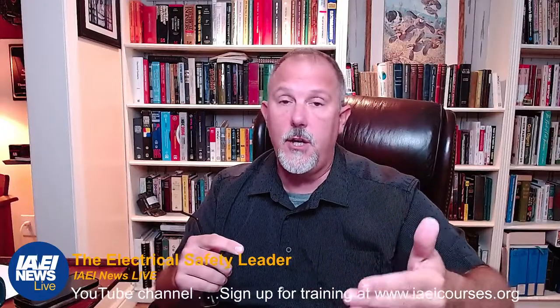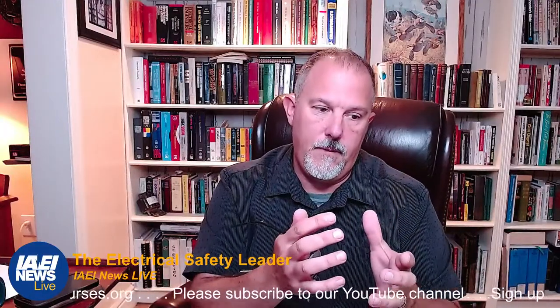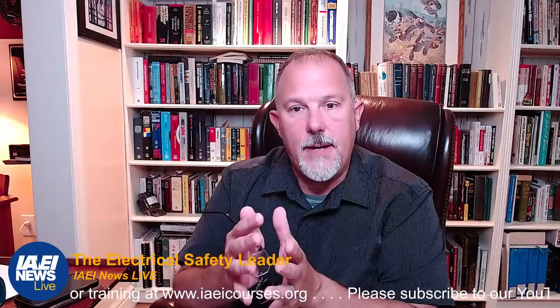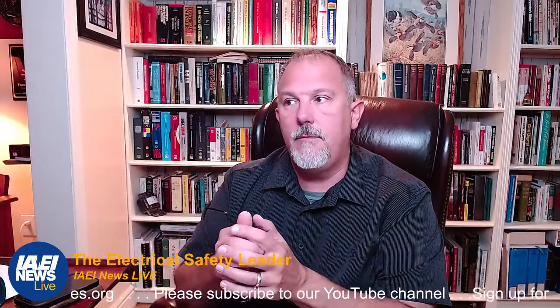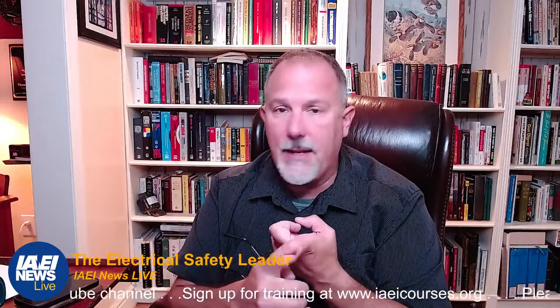What you always have to remember is when you install something per the National Electrical Code, it's not a 'set it and forget it' concept, because your power distribution system will change. Think about the parameters like available fault current — fault currents definitely do change, and those impact interrupting ratings and short circuit current ratings. That could also impact selective coordination performance of the overcurrent protective devices.